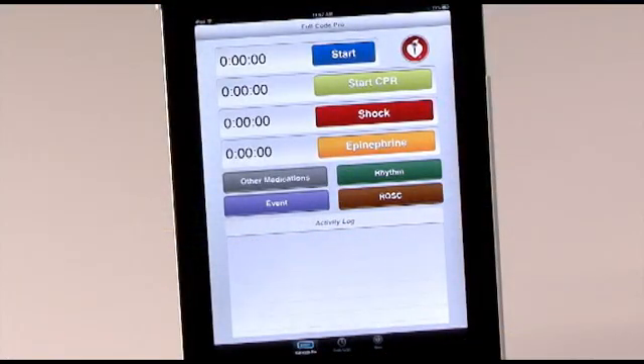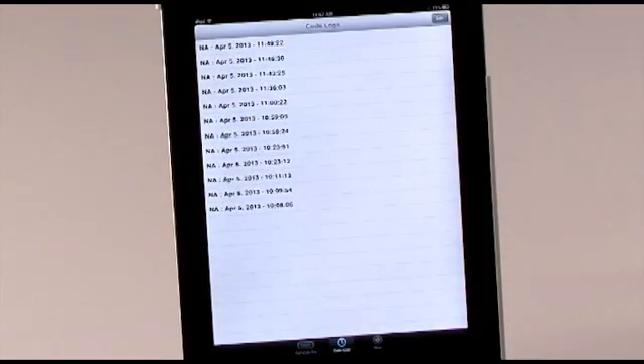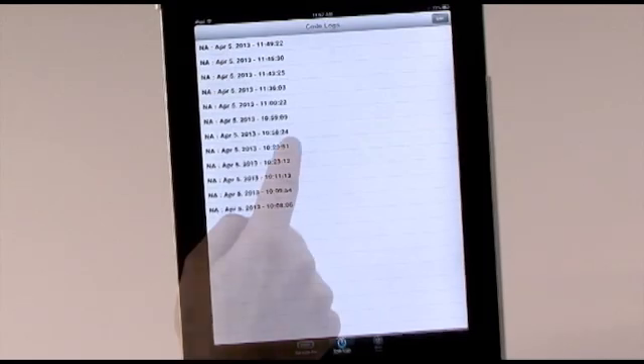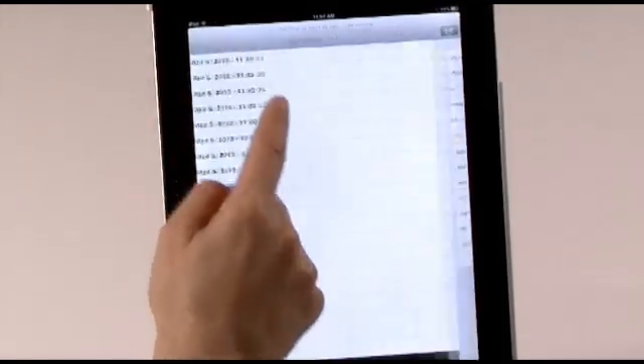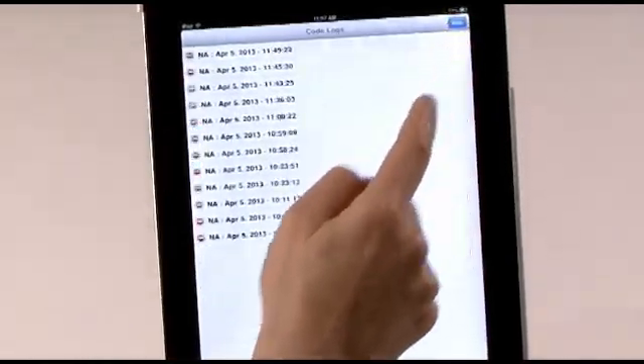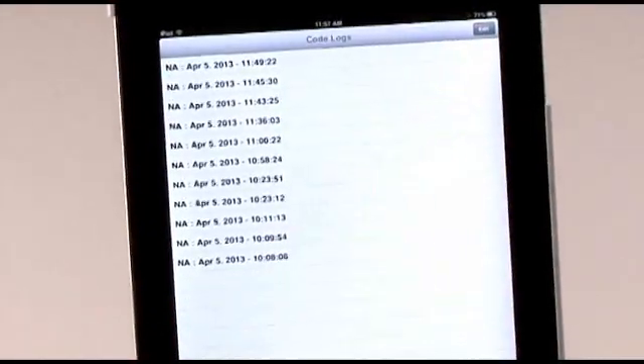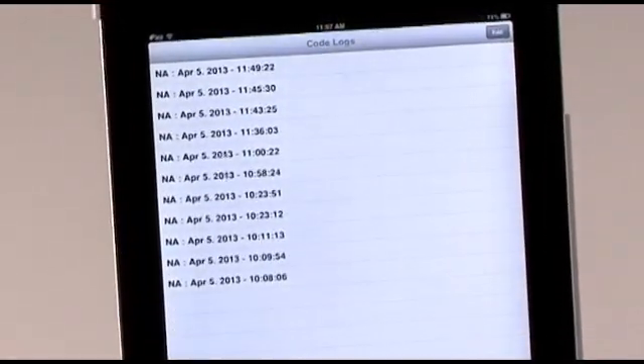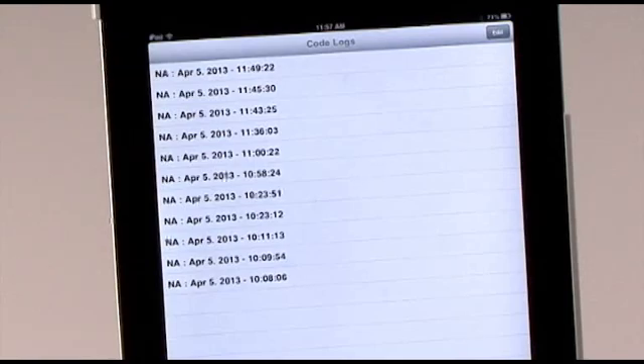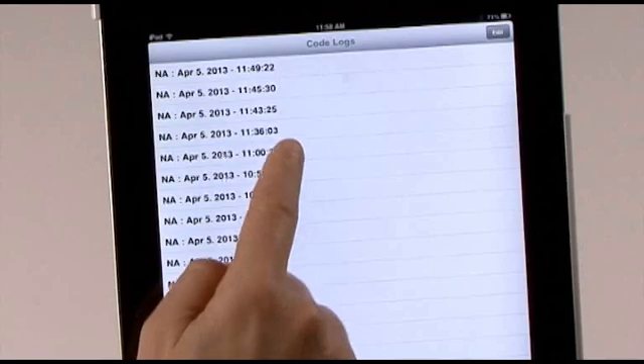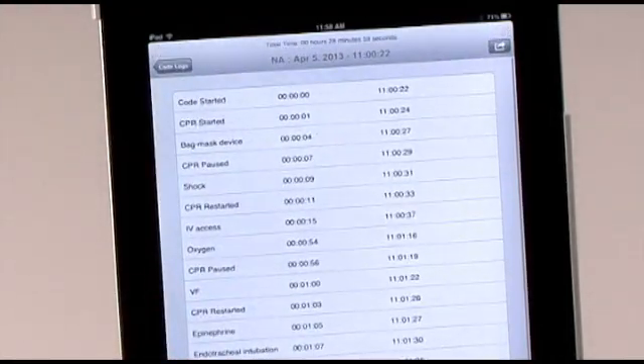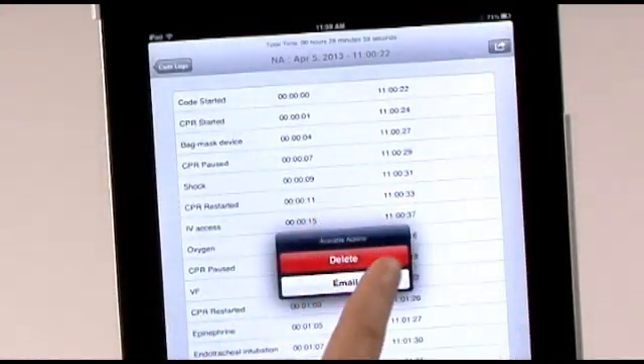The far left button takes you to the code screen. When you touch the middle code log button, you will see that all log files are kept here. You can review and delete log files at any time, but cannot revise them. Code log files can only be shared by email. The log files will remain on your device unless you have emailed them. To send a previous code log from the list of logs, touch the log that you wish to send, touch the arrow in the upper right, then hit Email.